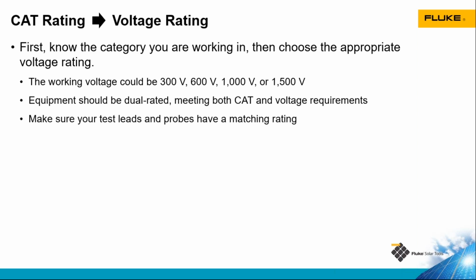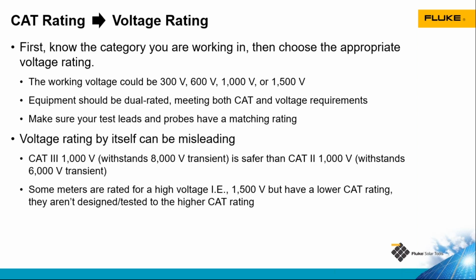When we buy our test tools, they're going to have a category voltage rating. The probes that come along with the test tool will have a matching category and voltage rating. It's important to make sure that our test leads have the same category and voltage rating as our test tool. What can often happen is, say, take a meter like our 393 clamp meter that's category 3, 1,500 volt rated. It comes with matching test leads, but if those leads should get damaged, it might be tempting to go into the shop and pull whatever test leads we have on the shelf, and chances are those are probably not going to have that category 3 1,500 volt rating. They're probably going to be something less. So we need to make sure that the test probes match the rating of the tool that we're using.